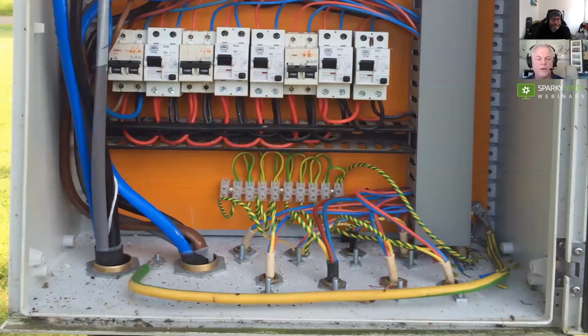All right. Also looking at the outgoing armoureds, they've been nutted and bolted. There's no earths on the armouring. They've been nutted and bolted onto a plastic enclosure, but there's no earth onto the armouring at all. So what you're saying is obviously the CPCs are here going into the conductors, but there's nothing going onto this. They've used a third conductor as the CPC for the outgoing circuit, but there is no earth on the armouring. And that is a requirement. You need to earth those armoureds because they're an exposed conductive part. So that's another C2.